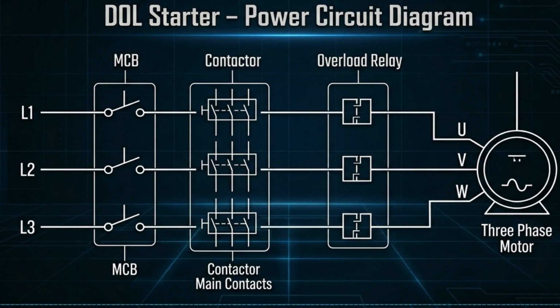It continuously monitors the current flowing to the motor. If the motor draws more current than its rated capacity for a certain period, the overload relay will trip and stop the motor to prevent overheating and possible damage. Finally, after passing through the overload relay, the three-phase power reaches the motor terminals, typically labeled U, V, and W.